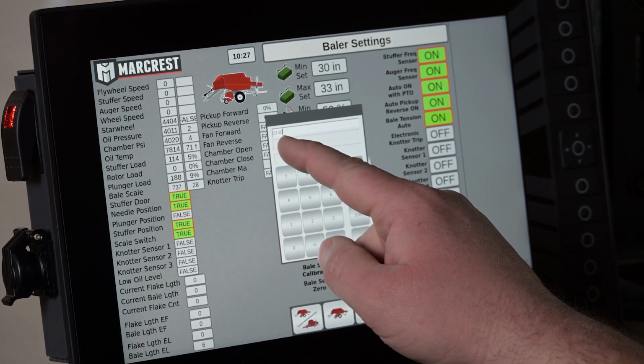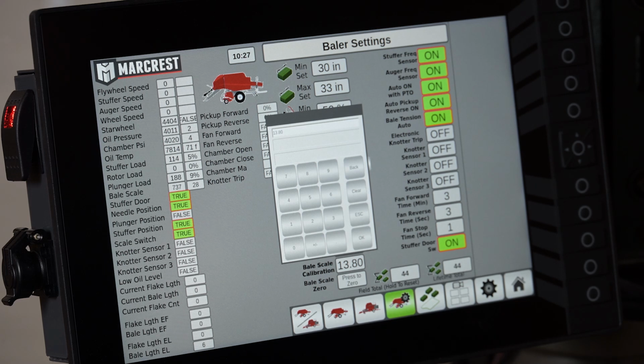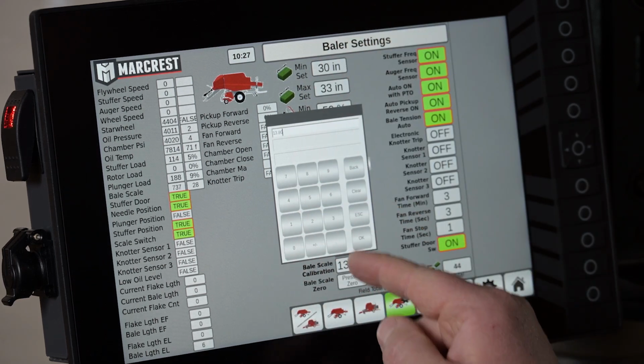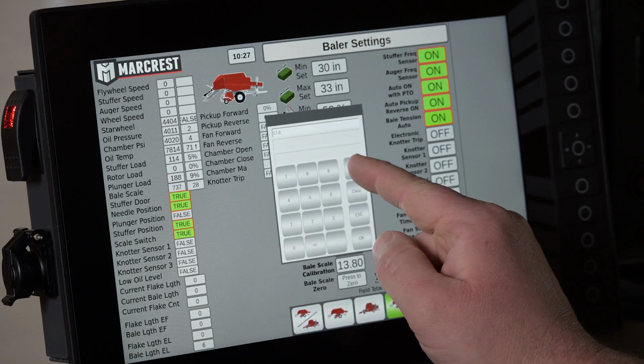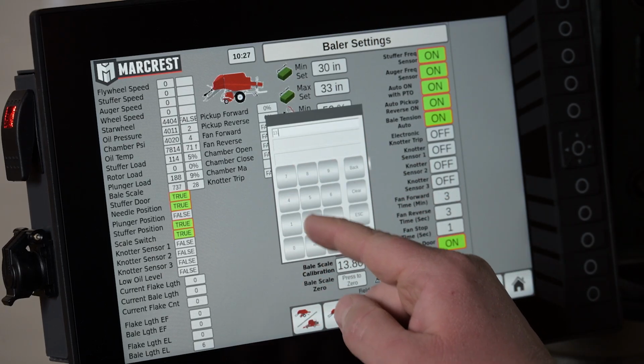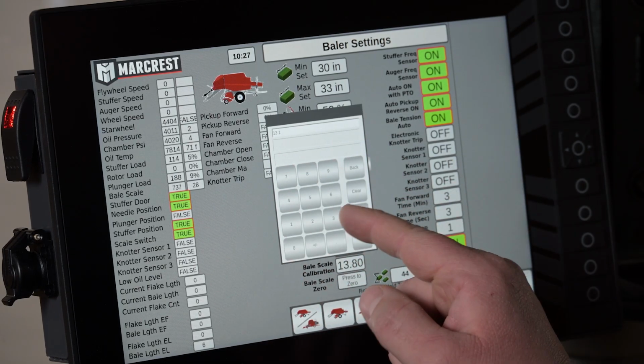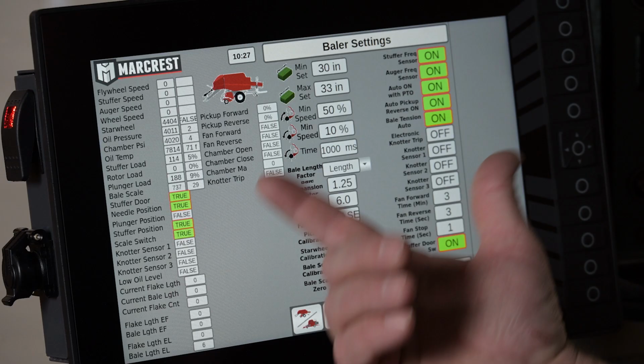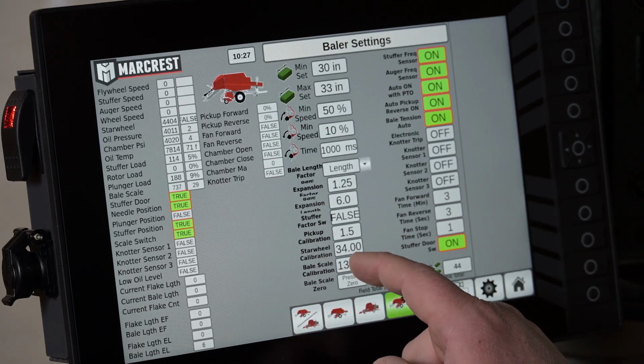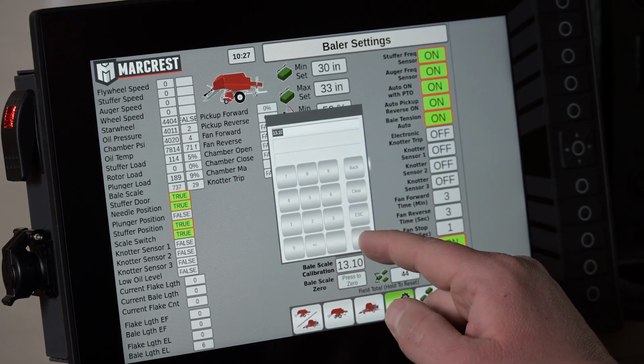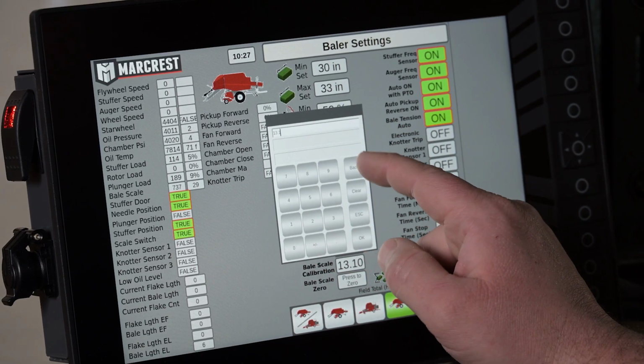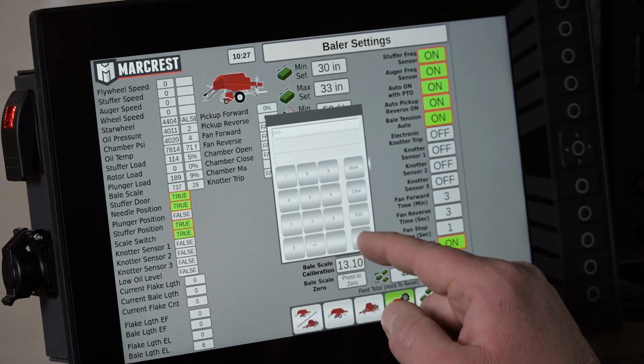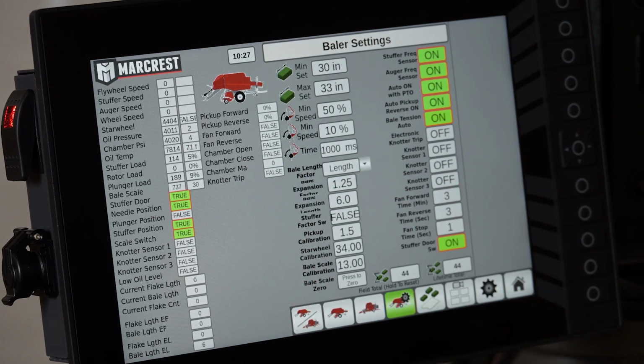So I have a value of 13.8 right now, and I want the scale to show more weight. So what I want to do is I want to manipulate that lower, so 13.1, to get that number higher. So it's showing 29, so I didn't go quite high enough, so I'm going to just try 13.0. So we're going to go 13.0, hit OK, and I'm showing 30 pounds. 30 pounds is what I have on the scale. So now I know I'm calibrated.